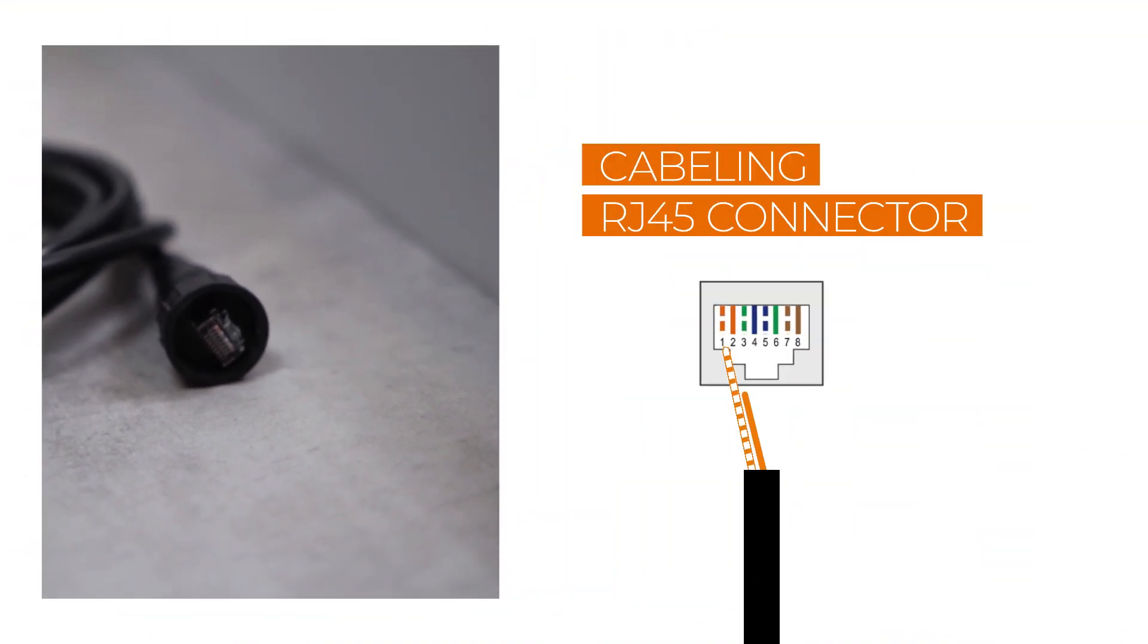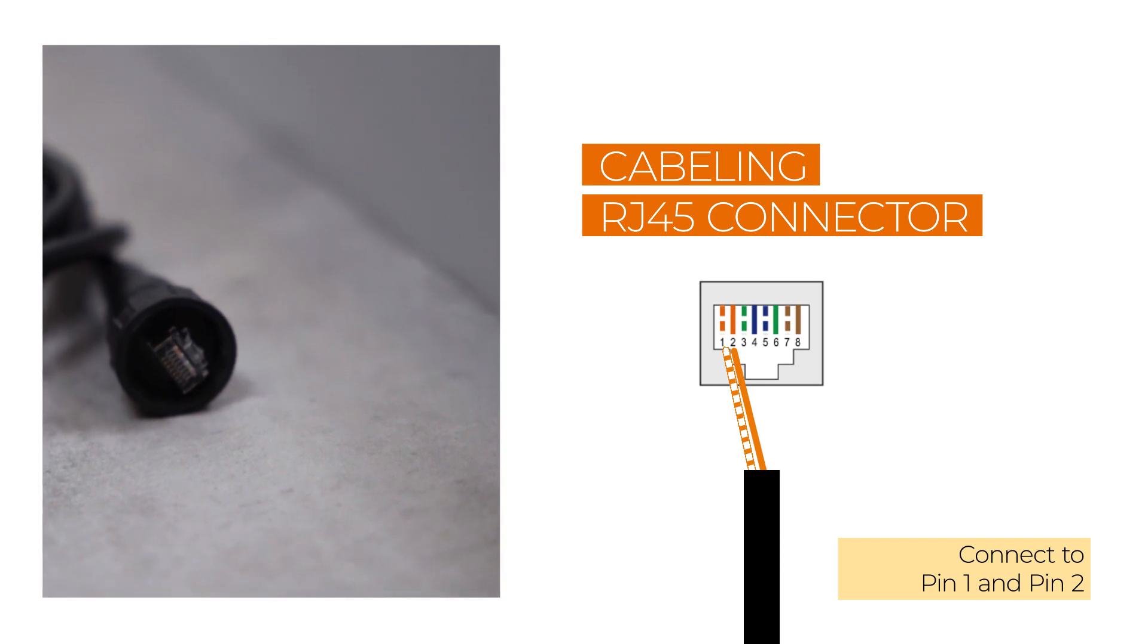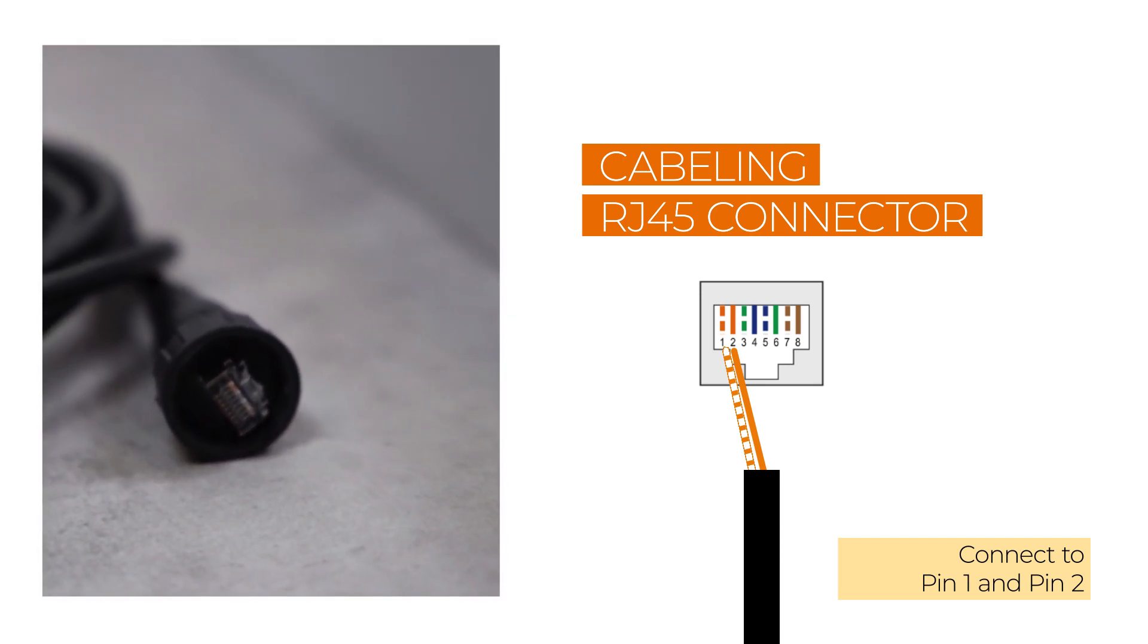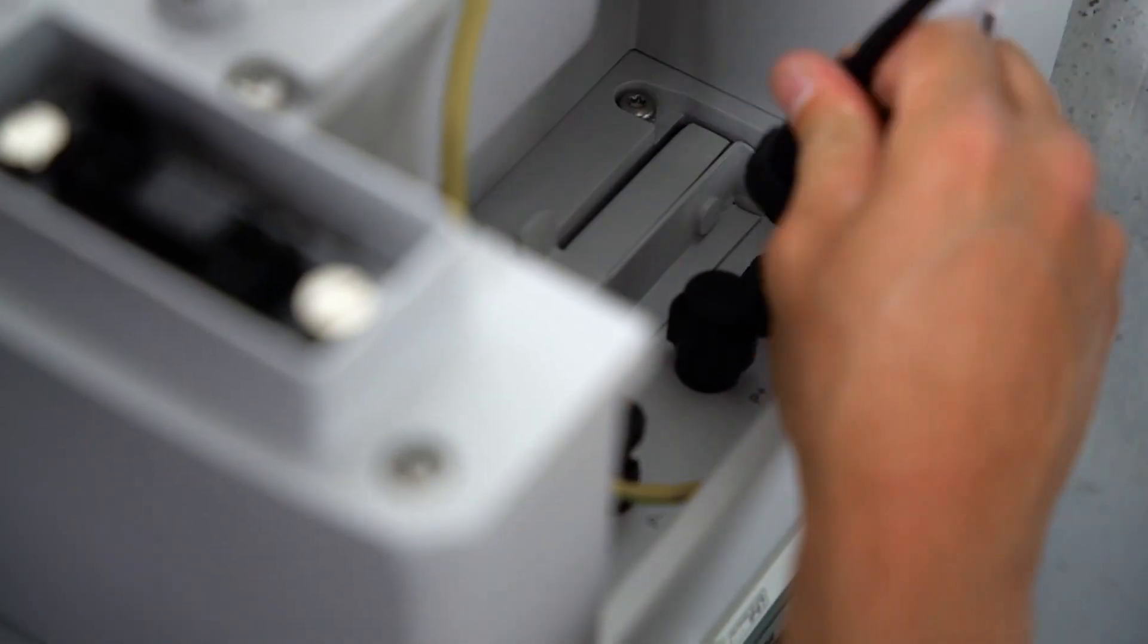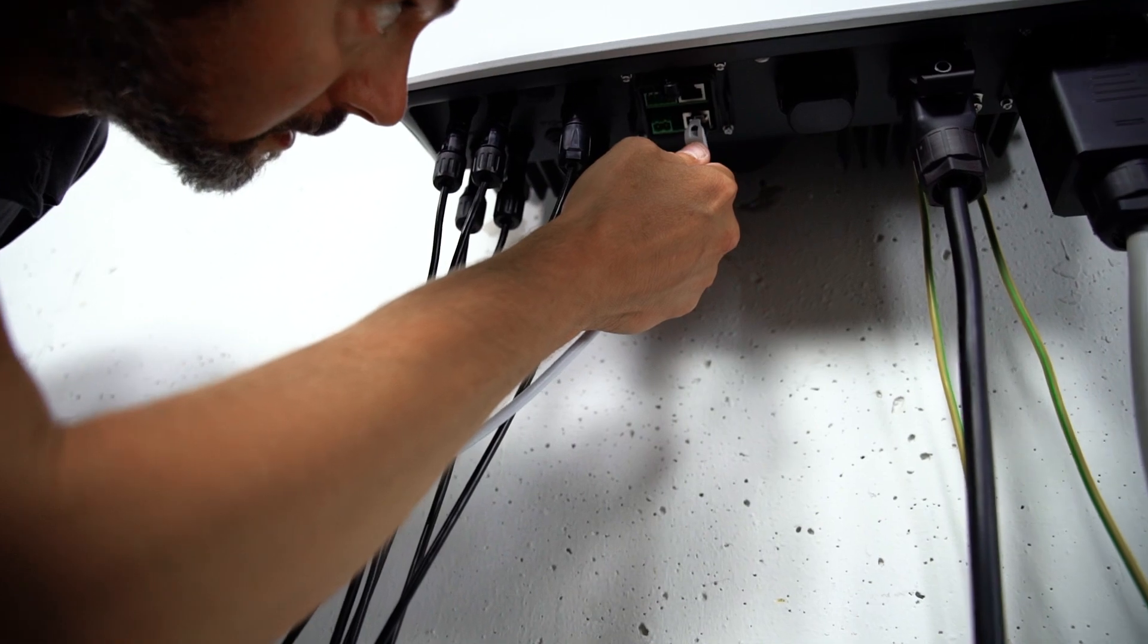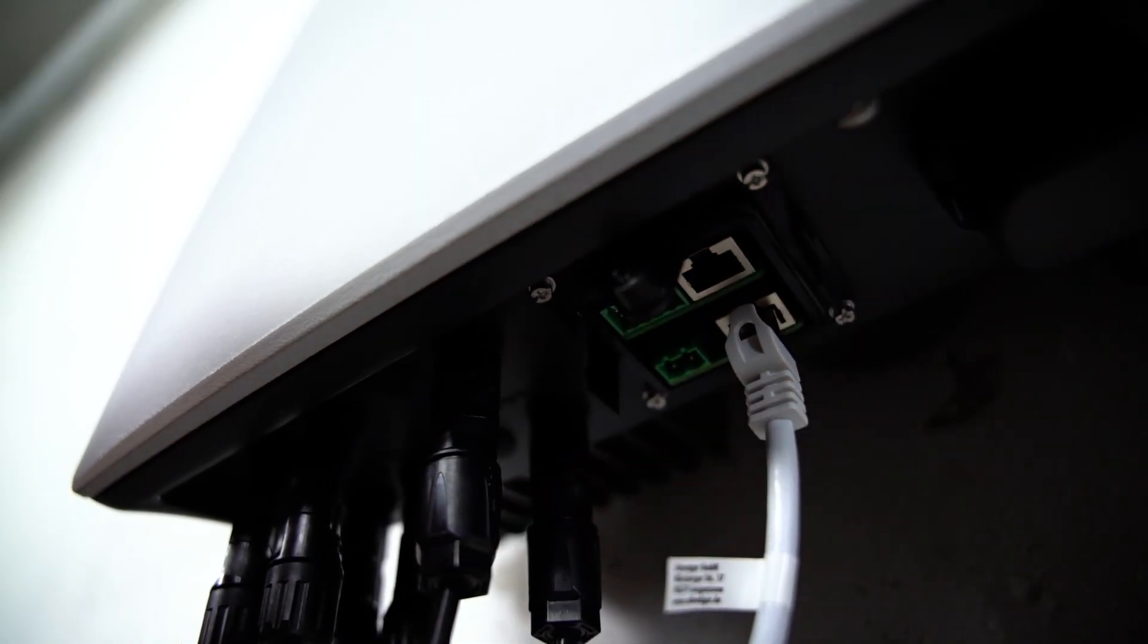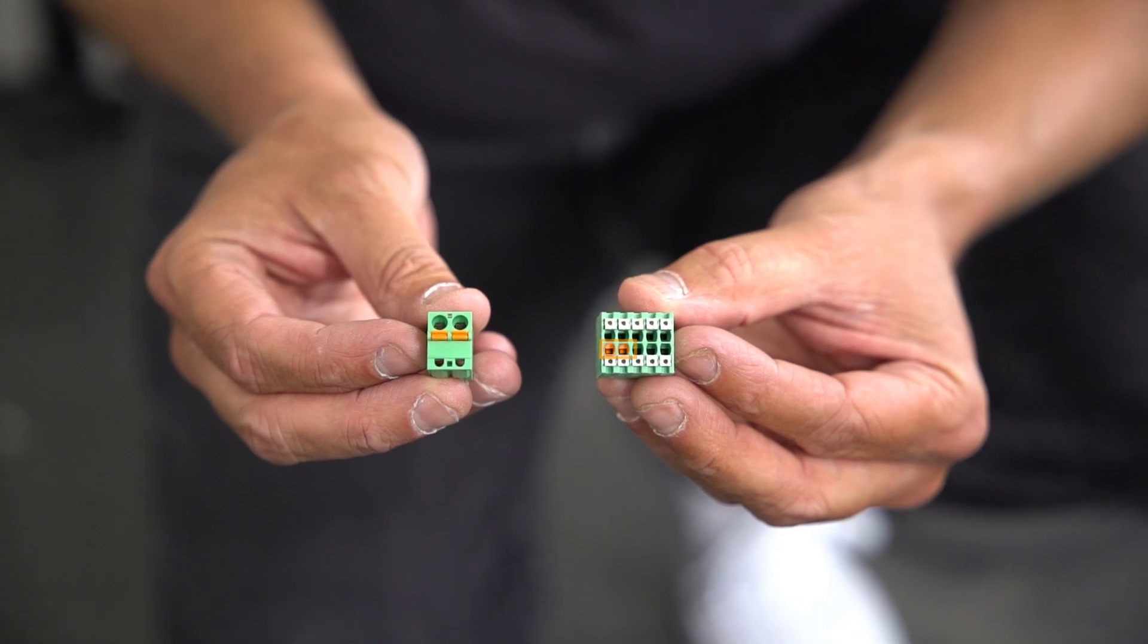The white-orange cable of the communication cable is connected to pin 1 and the orange cable to pin 2 on the RJ45 connector for the battery side. Connect the communication cable to the battery. The other end of the cable can be connected to the single-phase hybrid via ethernet or via the pins 2 and 4 of the communication plug.